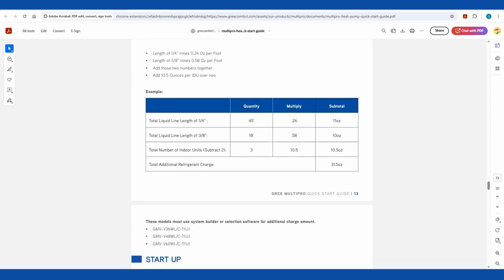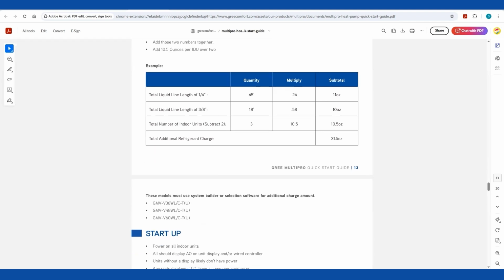So for an example here, if I had 45 feet of 1/4 times 0.24, that gives me 11 ounces. I have 18 feet of 3/8 at 0.58, that gives me 10 ounces. Total number of indoor units, I have 3, so I need to add 10.5 ounces because we got one more than the 2. That gives me a total additional charge of 31.5 ounces.